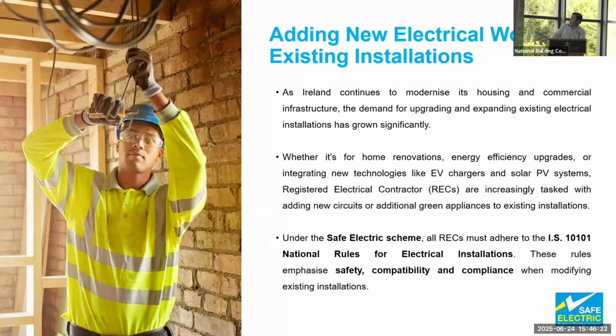So we are noticing a lot more, as we touched on, solar PVs and EV systems. EV chargers are probably, for us, one of the most frightening devices, because you're putting on over 30 amps of electricity, and that's a sustained load, and it can be on for over 10 hours in a night. That's a considerable amount of electricity to be running while you're asleep in your bed, so it has to be installed correctly, okay?